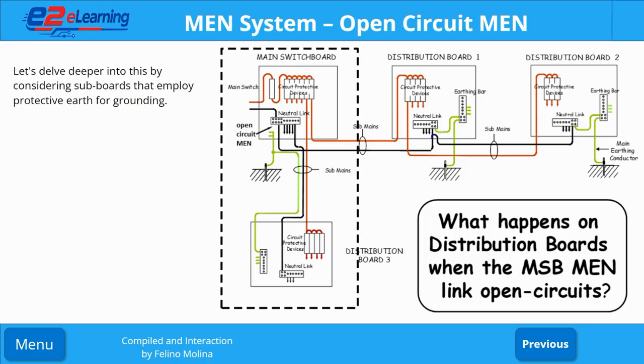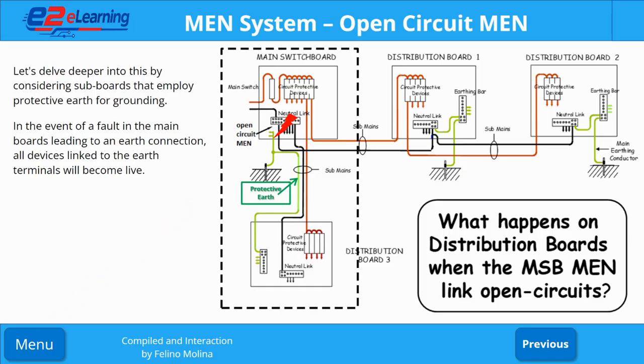Let's delve deeper into this by considering subboards that employ protective earth for grounding. In the event of a fault in the main boards leading to an earth connection, all devices linked to the earth terminals will become live. This encompasses the grounding elements within the subboard as well.